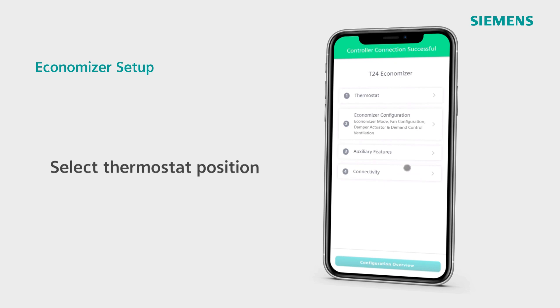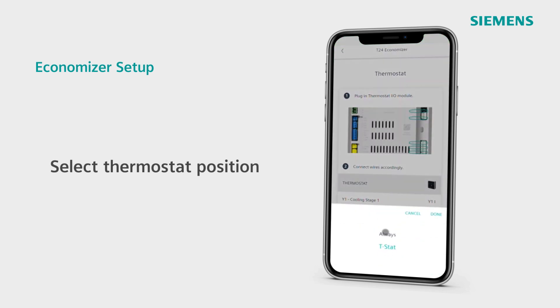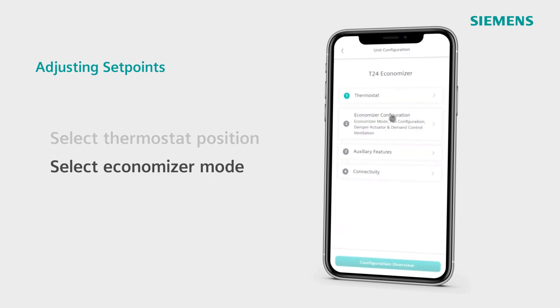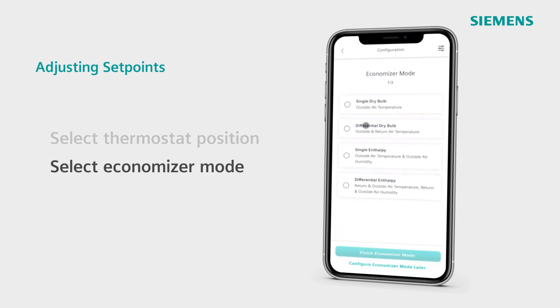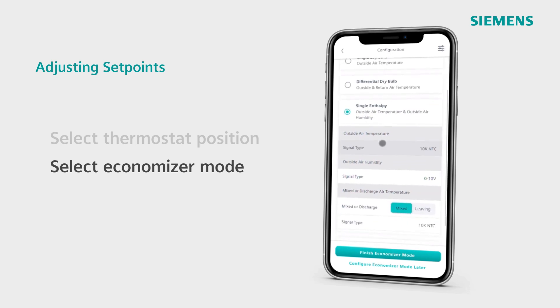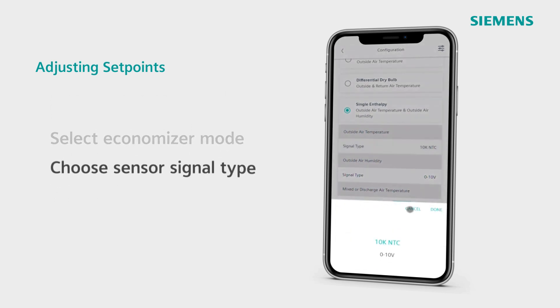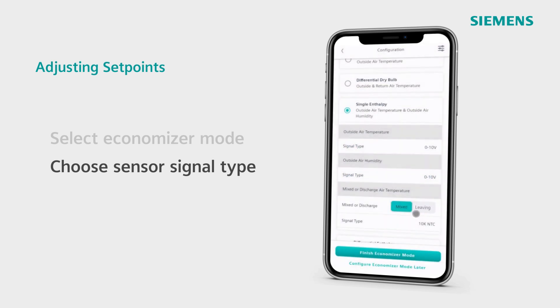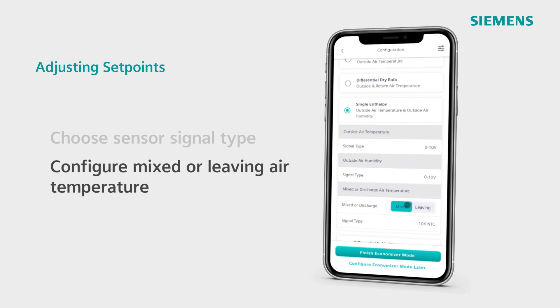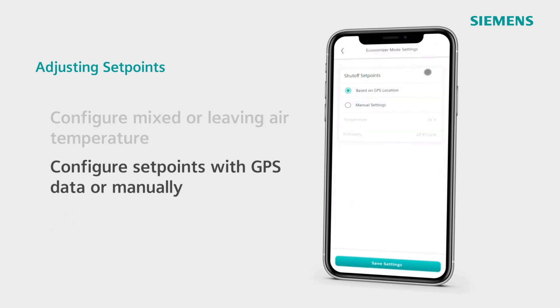Select your thermostat positions for occupancy, then begin configuration for the Economizer. Choose an Economizer mode according to your sensors, then choose the signal type for each of these sensors and indicate whether or not your system uses mixed or leaving air. GPS functionality also allows you to configure shutoff set points according to the ASHRAE climate table based on GPS location or by manual settings.